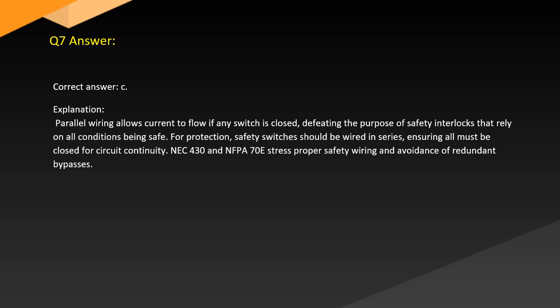Answer. Correct answer: C. Explanation. Parallel wiring allows current to flow if any switch is closed, defeating the purpose of safety interlocks that rely on all conditions being safe. For protection, safety switches should be wired in series, ensuring all must be closed for circuit continuity. NEC 430 and NFPA 70E stress proper safety wiring and avoidance of redundant bypasses.